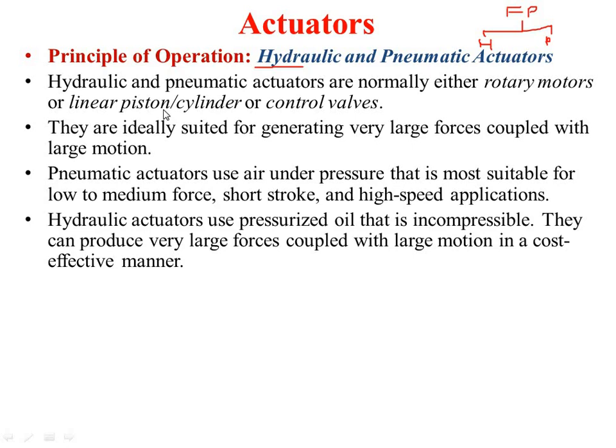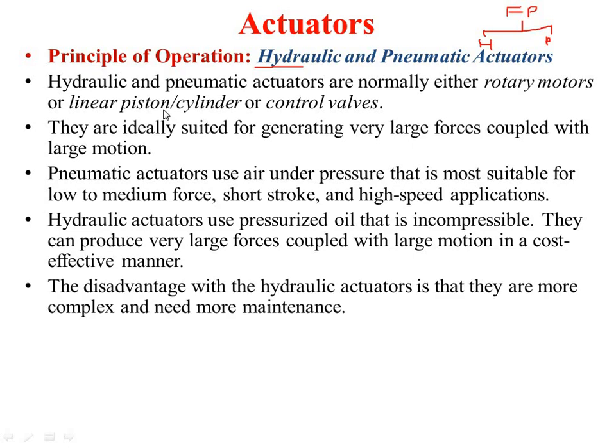Whenever you are going from medium to large forces, generally hydraulic actuators are preferred over pneumatic actuators, with the motion in a cost effective manner, and most of the time the air and the oil can be used again and again. But as compared to pneumatic, the hydraulic actuators need more maintenance. So the disadvantage of a hydraulic actuator is that it is complex and needs more maintenance.